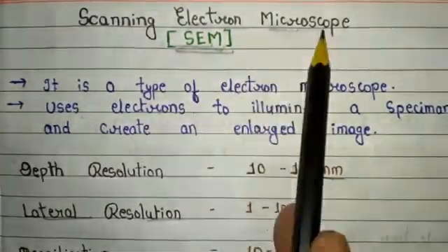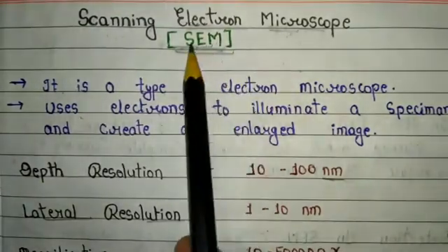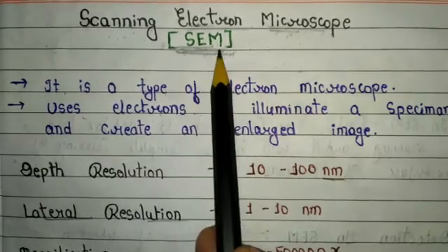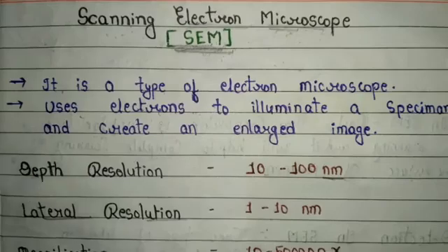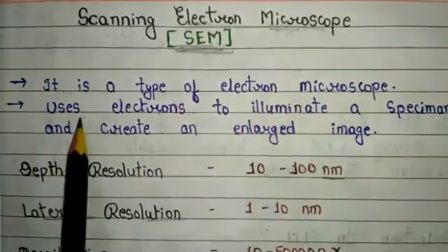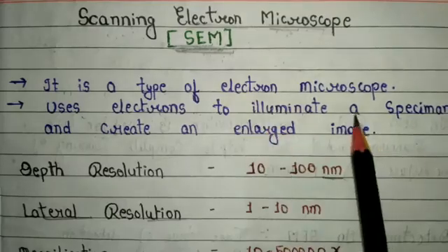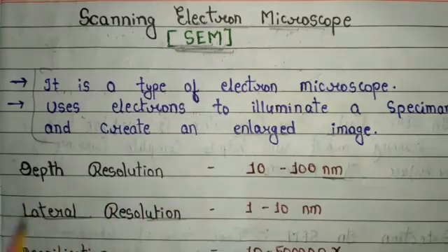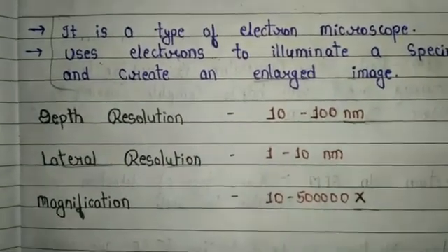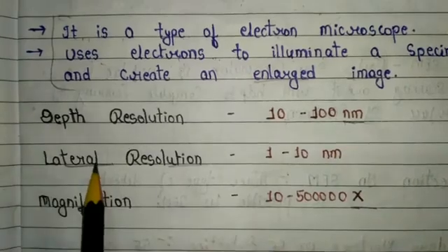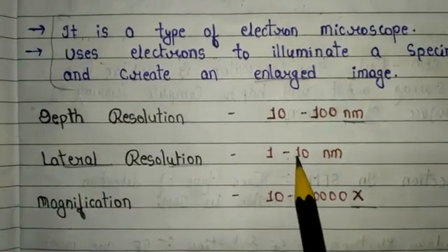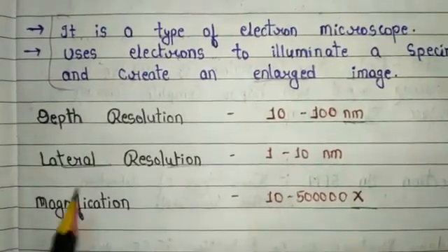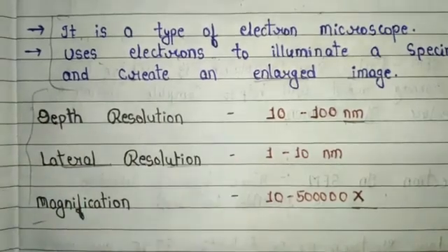Electron microscopes are basically two types: SEM (scanning electron microscope) and TEM (transmission electron microscope). In this particular video we completely discuss about SEM. The basic introduction of SEM is that it is a type of electron microscope that uses electrons to illuminate a specimen and create an enlarged image. The depth resolution of SEM is 10 to 100 nanometers, lateral resolution is 1 to 10 nanometers, and magnification power is 10 to 5 lakh X.